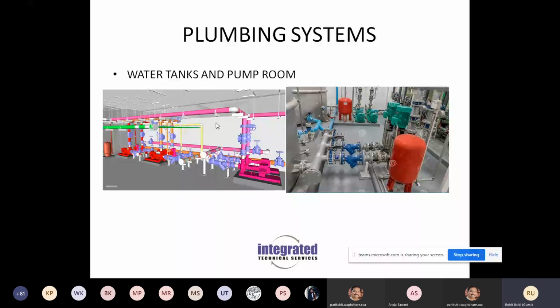Now, if you can see on the left-hand side, you will see the firefighting pumps, which are in red. These firefighting pumps supply water right from the bottom, which is usually in a basement, to the top terrace level of the building, and the water is available to fight fire all the time. These firefighting systems, as per law, are always under pressure. They're always pressurized. So at any given point of time, if you go and open a valve in a firefighting system, the water will start to flow at a very high pressure, and the pumps will start automatically once it senses that a valve has been opened. I'll delve into further detail on firefighting in the next module.